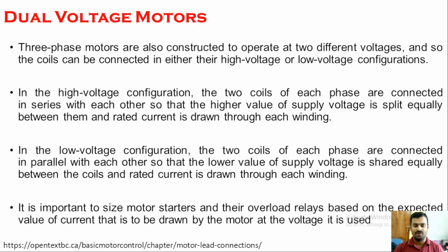So if you have a high voltage motor configuration, the current ratings will be lower. On the other hand, if you have the high current configuration, that is the low voltage configuration, the current ratings will be higher. So based on which configuration you are going to use this motor, the overload relays and the motor starters will be chosen.